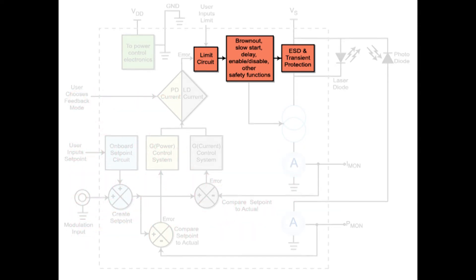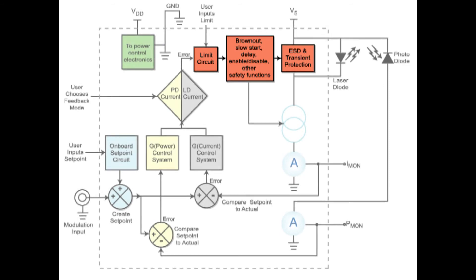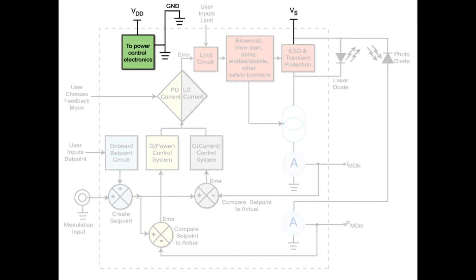Power must be provided to the control electronics and the current source. This can take the form of a DC power supply for an OEM module or an AC input connector and cable for an instrument.